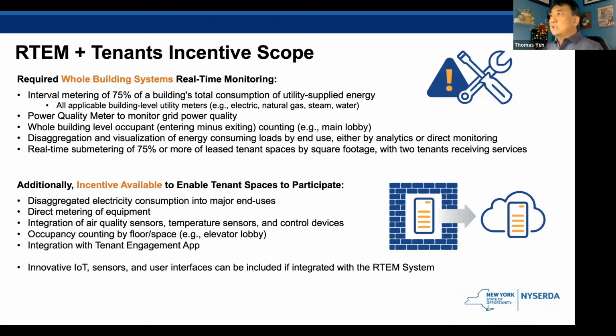Additionally, the building's utility and tenant usage must be disaggregated and visualized by significant end uses, such as lighting, heating, cooling, ventilation, perhaps data centers, et cetera. We will allow disaggregation using analytics or adding submeters by end use, such as installing a meter or a CT on all the lighting panels. You can also do it by a combination of analytics and submetering.